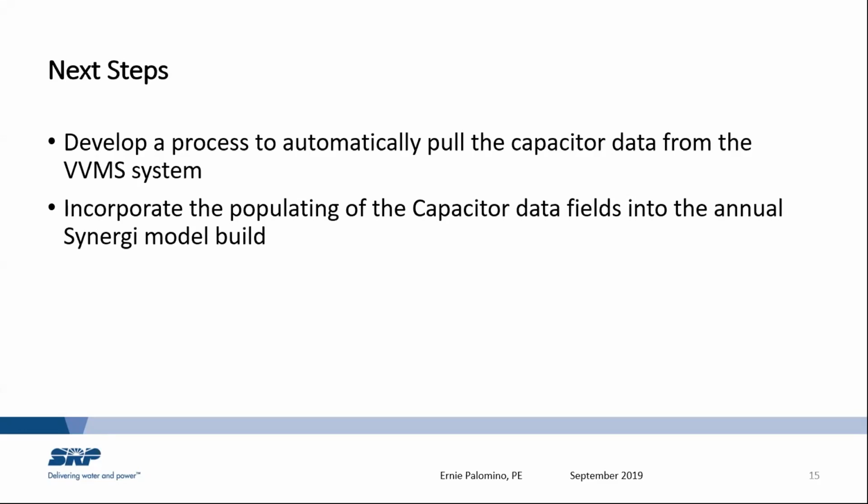Oh no, we're not. That was just for that. That was for the study. I mean, I guess what I'm saying is when we do our study right now in our model, we just turn them all on. But yeah, you're right. In the field, they're not all turned on. In fact, when I actually do a capacitor study every year, based on my study, I'm assuming they're all on. So I'll say, oh, I need a capacitor there. And then I go to cap techs and they'll verify. Sometimes they come back and say, oh, we already have cap 8 there. It was turned off. So I don't need a new cap there. They just need to turn that one on. So yeah, it's only in the model that we have everything turned on.